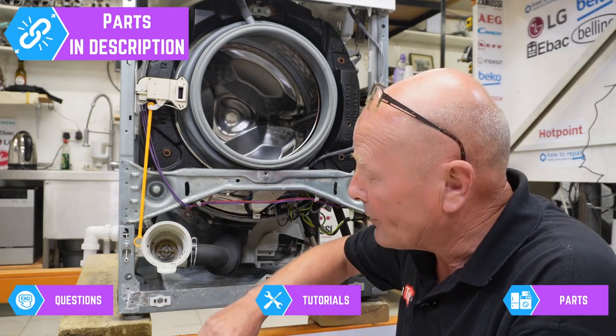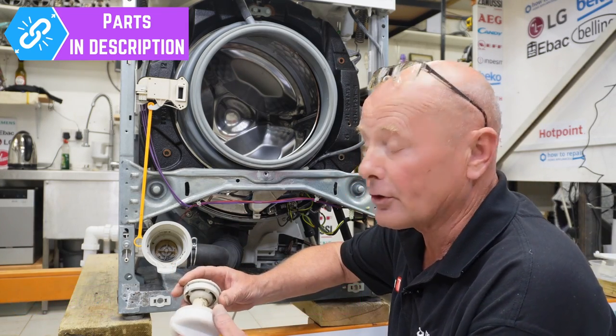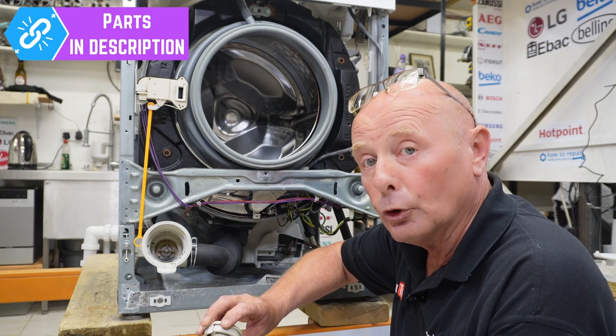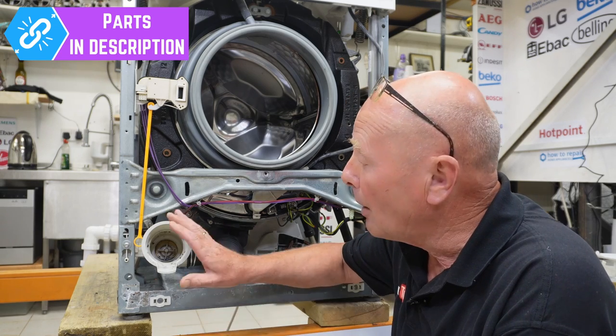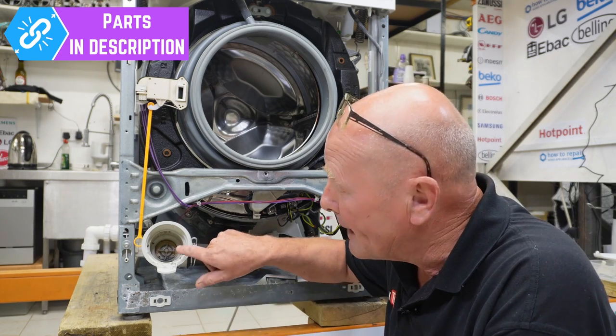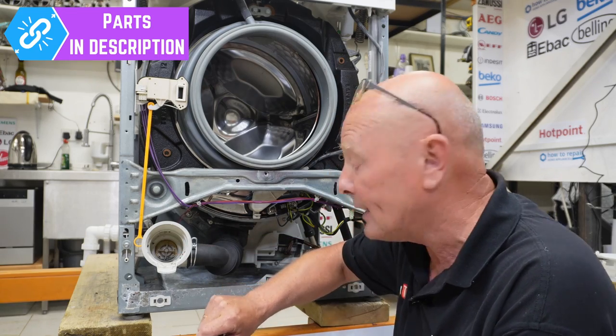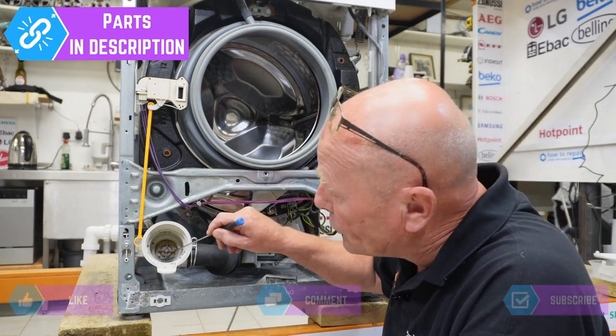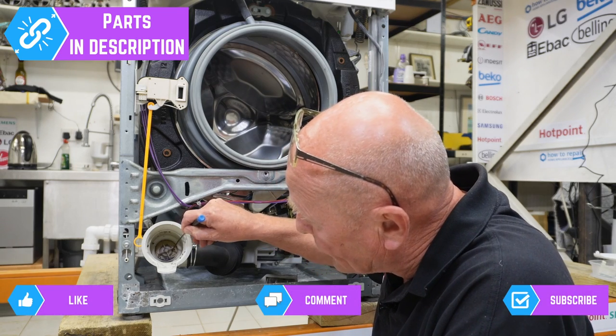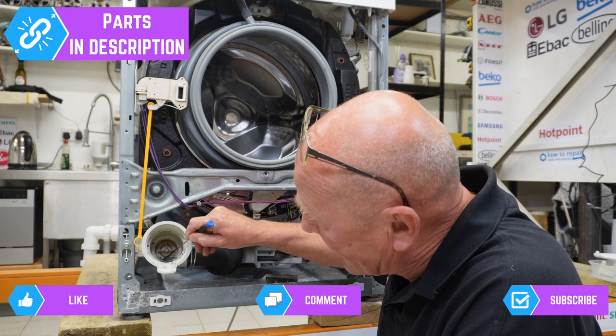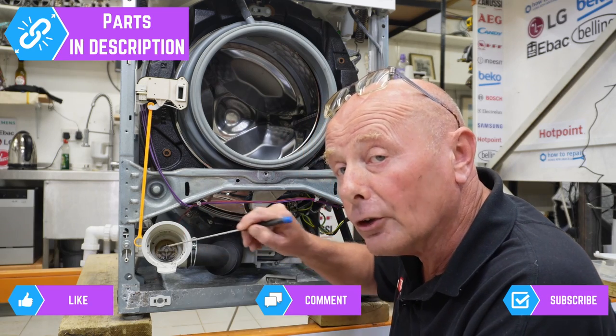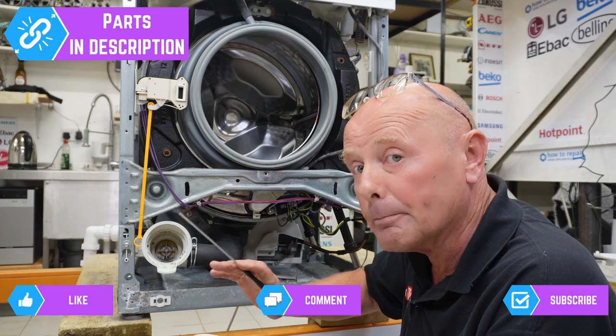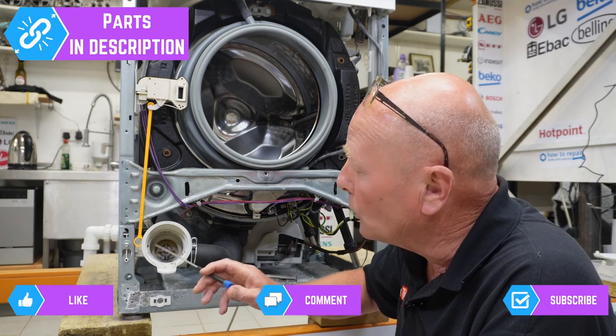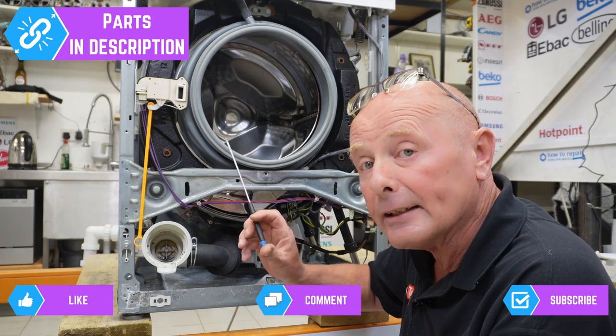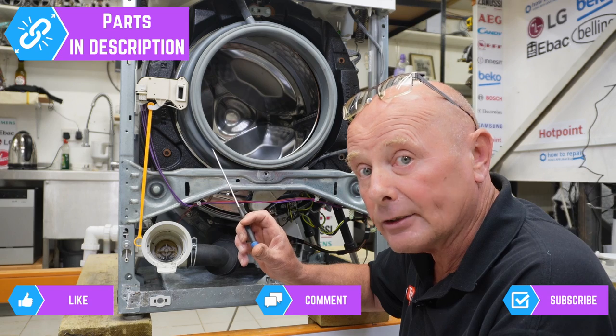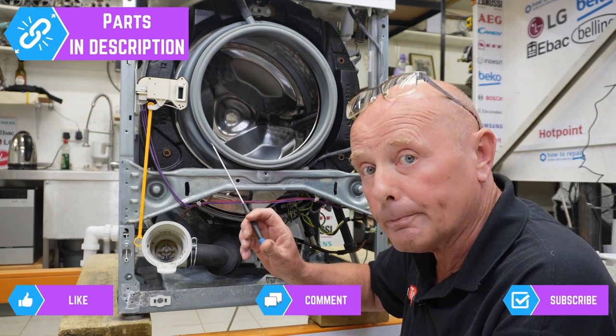The pump itself has an impeller and a filter system. If this gets blocked, this would also cause the same problem. Pumps can be tested on the bench to make sure that the impeller turns freely. You can also use a screwdriver to make sure the pump is rotating. They sometimes have a magnetic feel to them, and this is because of the design of the pump. They're a magnetic type pump motor. From here, the water then goes through to the container that I said, which we'll have a look at in a second, and then goes into your drainage system.